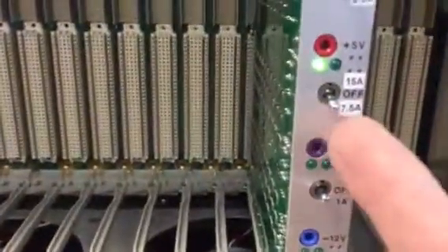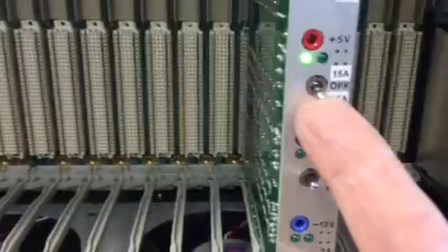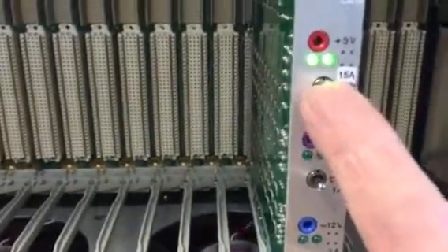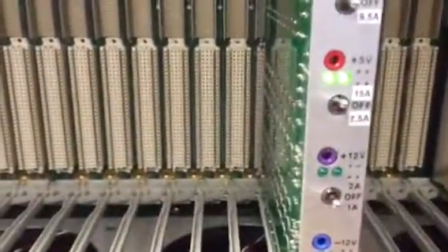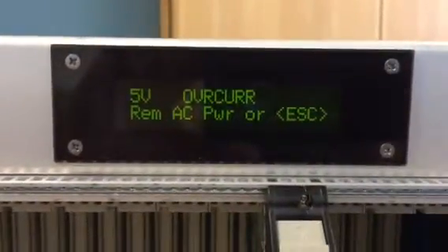I'm going to turn it to 15 amps, which should make the chassis fail because I set it to turn off at 13. So I go up to 15 amps and the chassis turns off for over-current.